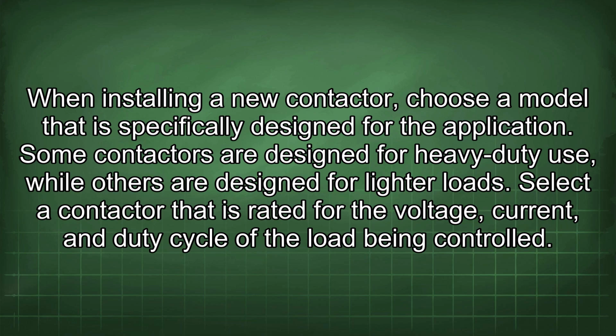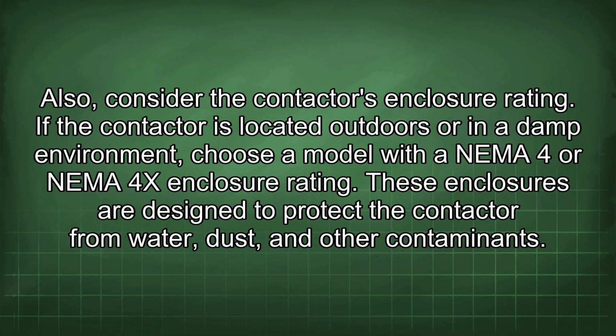When installing a new contactor, choose a model that is specifically designed for the application. Some contactors are designed for heavy-duty use, while others are designed for lighter loads. Select a contactor that is rated for the voltage, current, and duty cycle of the load being controlled. Also, consider the contactor's enclosure rating. If the contactor is located outdoors or in a damp environment, choose a model with a NEMA 4 or NEMA 4X enclosure rating. These enclosures are designed to protect the contactor from water, dust, and other contaminants.